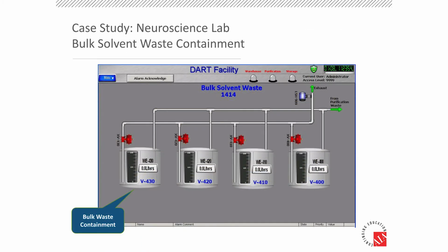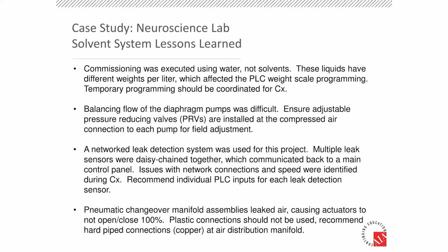Bulk waste, 4 bulk waste tanks. They basically stage with these valves. If this one gets too high, we close it, we open the next one, and that tells the facilities team, hey, we've got tank A is full, let's get that out of here. Let's quick disconnect that, get it out, put a new tank in, and keep going. So from a commissioning standpoint, this was a really fun thing to commission, just due to the complexity and the levels of alarm scenarios.